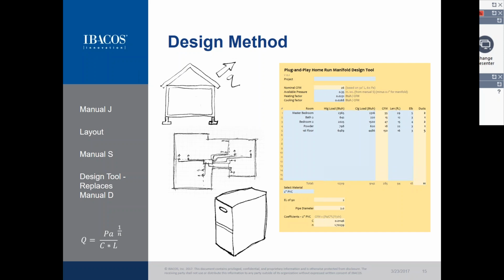So if you have 2 ducts that each are delivering maybe 35 CFM going to a room, and that room needs 65 or 70 CFM, that room would get 2 ducts. Under the conventional mindset, that room might get, say, a 7-inch duct coming off of a main trunk. So that's the major difference here with this approach compared to the conventional systems.